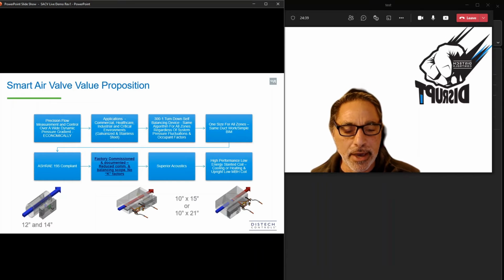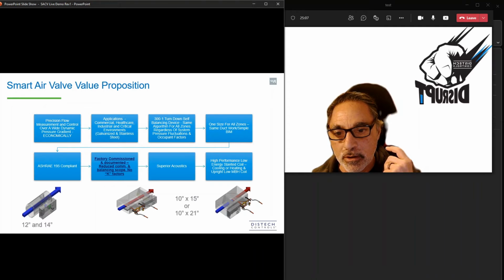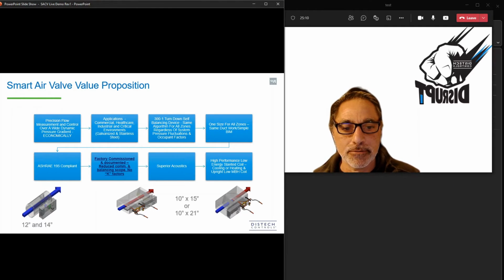And what we have here is a BACnet IP controller ready to go out of the box. It's configured. It has its commissioning paper ready to go. And when you get this out in the field, there is no balancing. Again, I'm going to say that. There is no balancing. There are no K factors. All you have to enter, which you could do through the stat or a balancing tool, is only the maximum CFM and minimum CFM. I said balancing tool just because I'm an HVAC, controls guy. I've used that multiple times in my previous jobs, and I need to get rid of that term. But there is no balancing here.